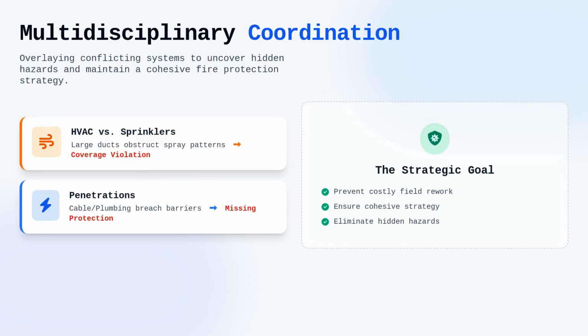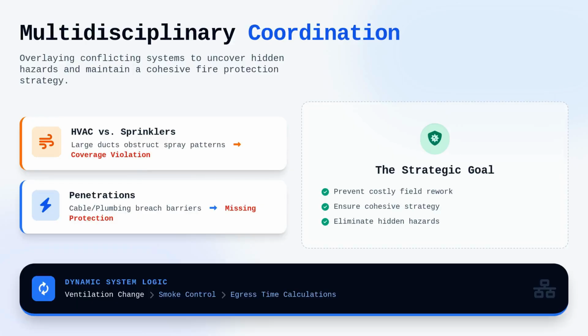Identifying these conflicts before they become field issues prevents costly rework and, more importantly, ensures the fire protection strategy remains cohesive. We must treat every plan as a dynamic system where a change in ventilation can influence smoke control and, by extension, the egress time calculations we previously audited.